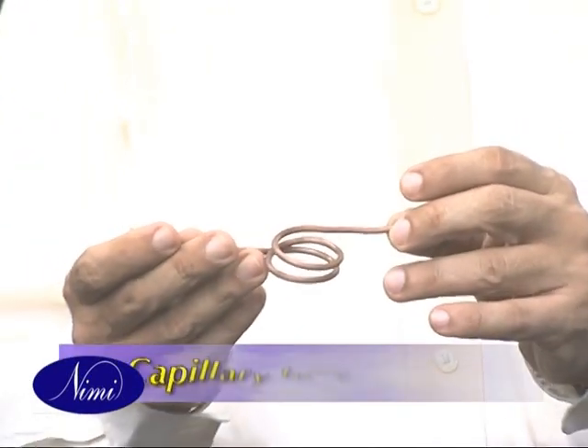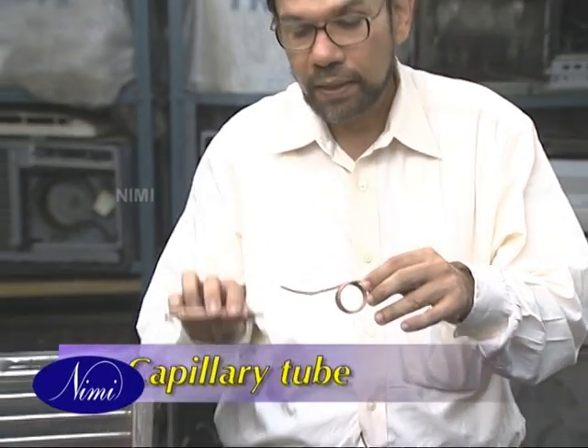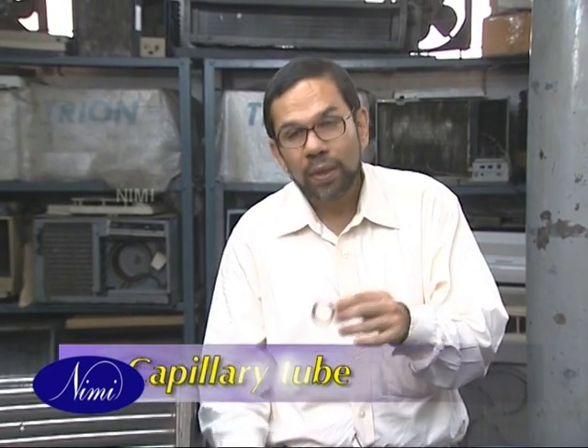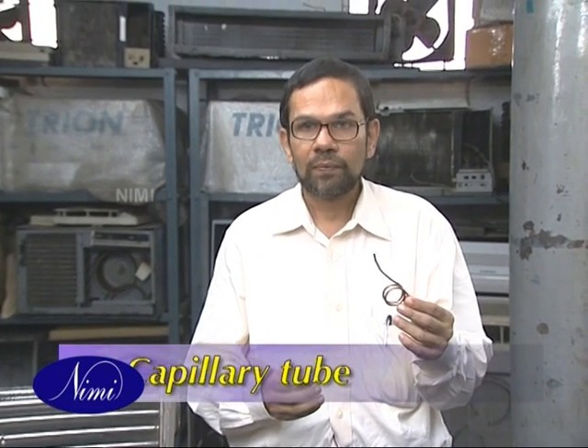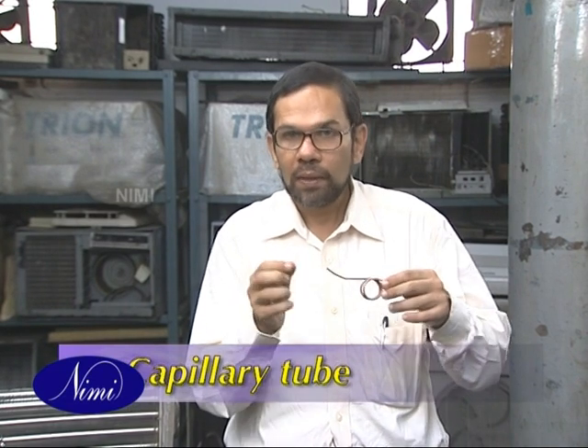This is the capillary tube and is fitted just after the strainer dryer. What is the purpose of this capillary tube? It is a very fine bore copper pipe which creates a pressure difference between the condenser and the evaporator. So you have a high pressure, high temperature condenser and a low temperature, low pressure evaporator or cooling coil. This creates a sudden change, we can say an expansion of the refrigerant before it goes to the evaporator, where it suddenly cools.